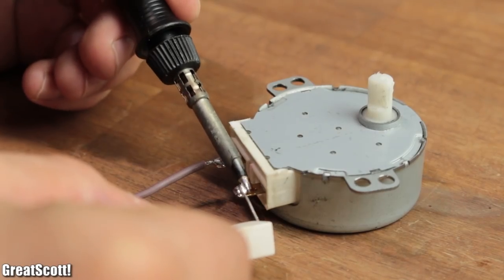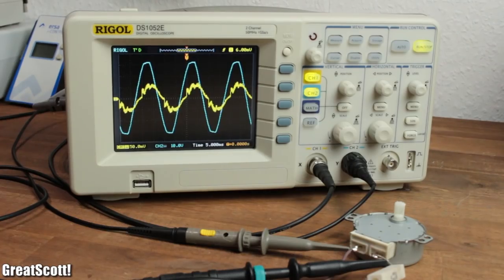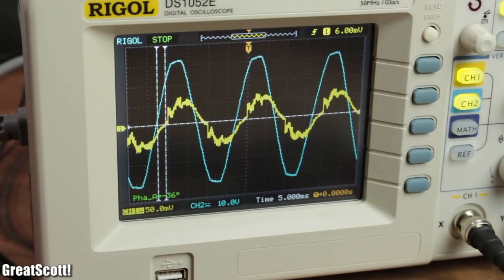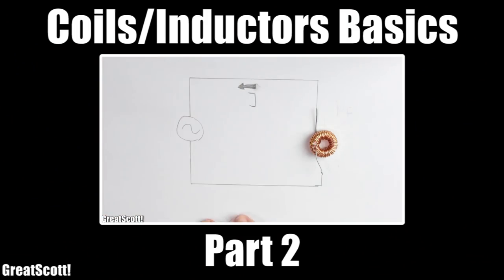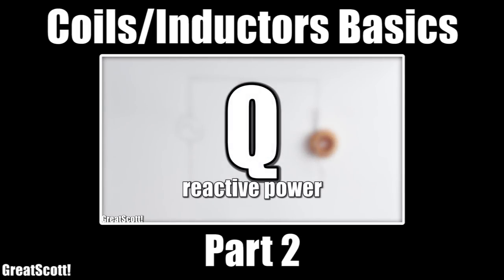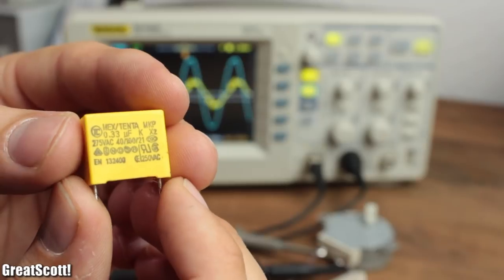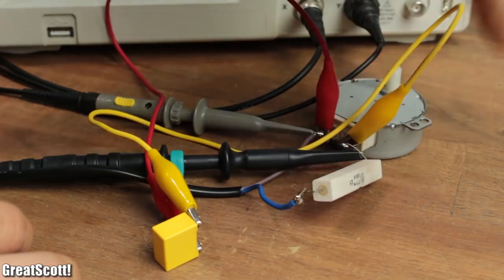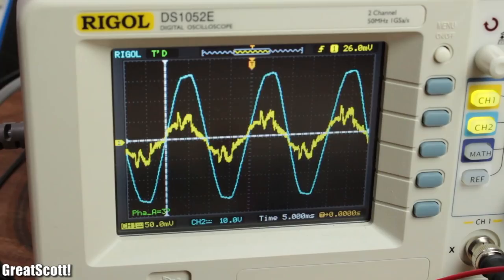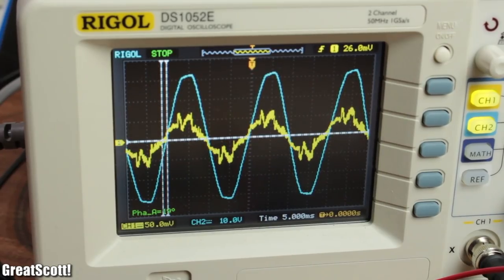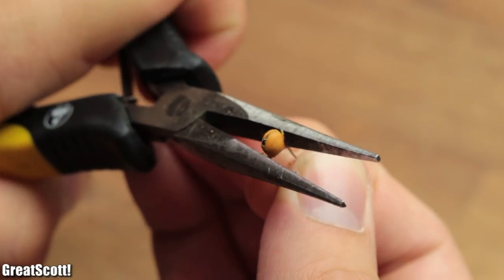Lastly, let's hook up our microwave motor to our power line and we see that it still creates a phase shift of around 36 degrees. As I told you before, this creates reactive power, which strains our power grid. In order to get rid of this, we can add a capacitor in parallel, which also creates a phase shift, but in the other direction. This compensates our inductive load and relieves the power grid from the reactive power.